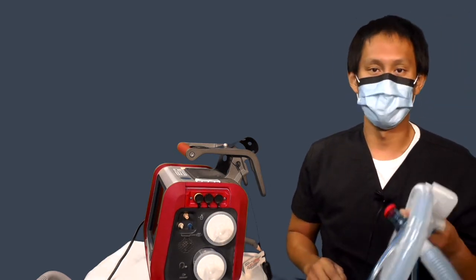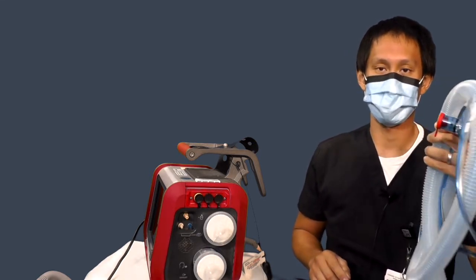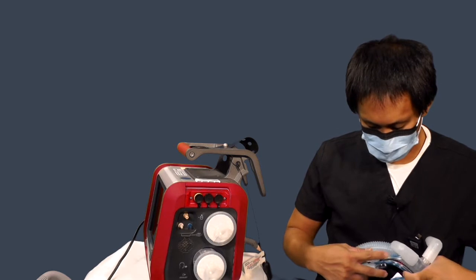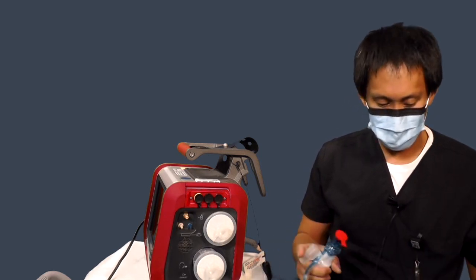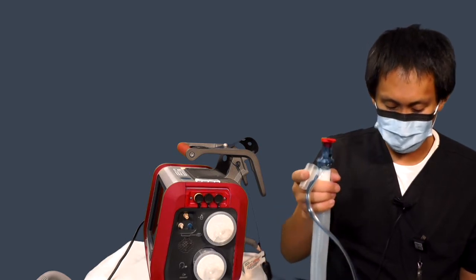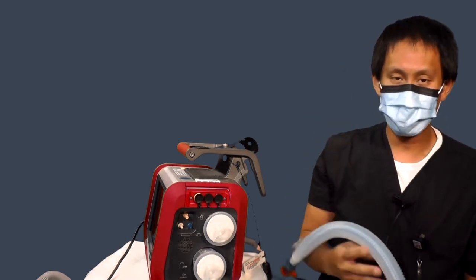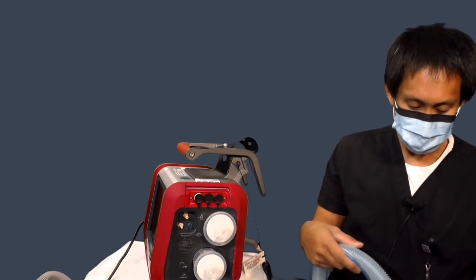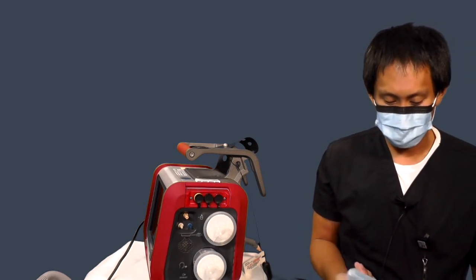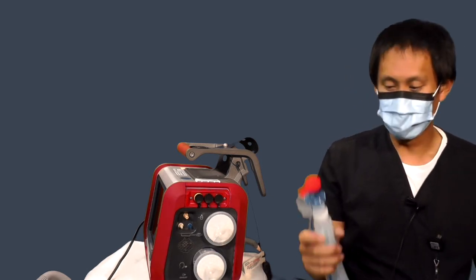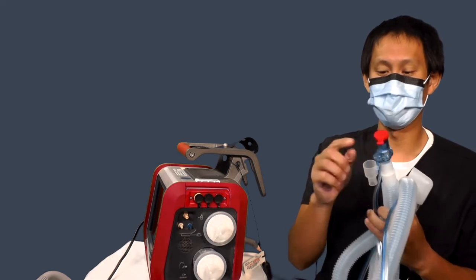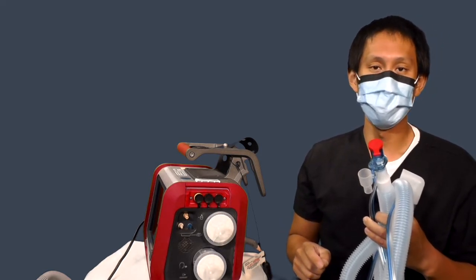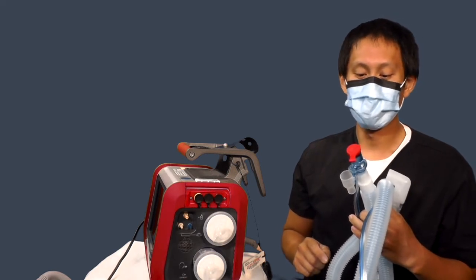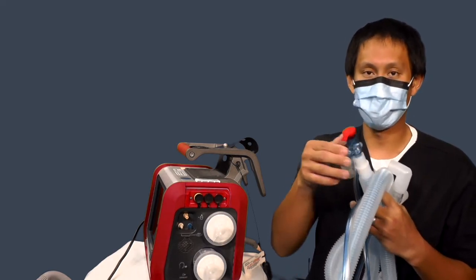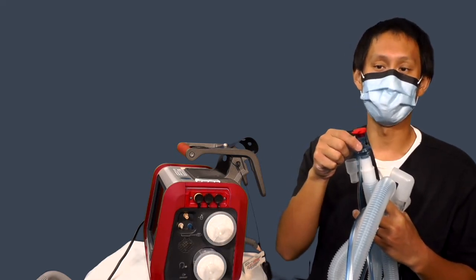If you're using the Hamilton circuit, it comes in a kit. It looks something like this. It's a single limb dual lumen circuit. By that I mean it has the inspiratory and the exhalation inside one single tube. And if you're using the Hamilton circuit, it will include a flow sensor, which is this darker blue piece at the top. If you're using a non-Hamilton circuit, which you can do, you would have to buy or get a flow sensor separately.